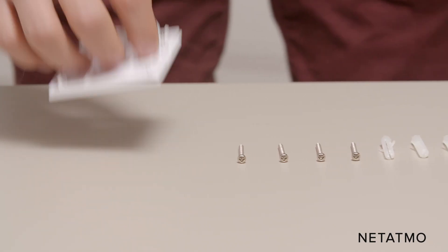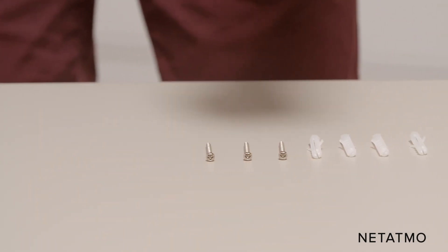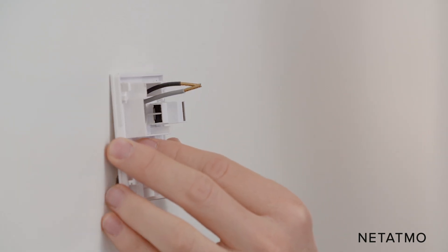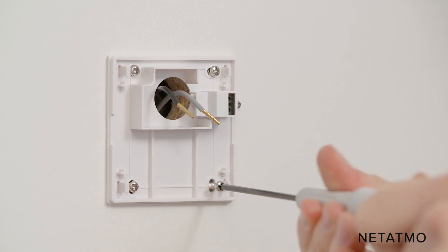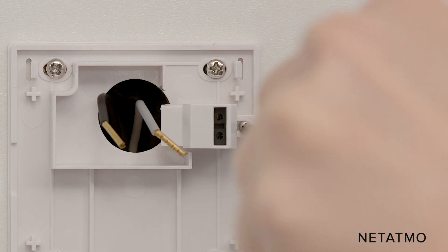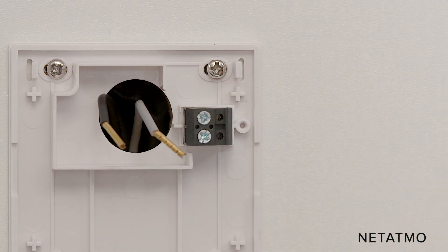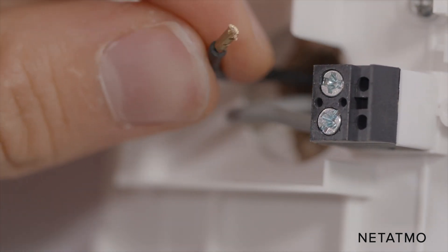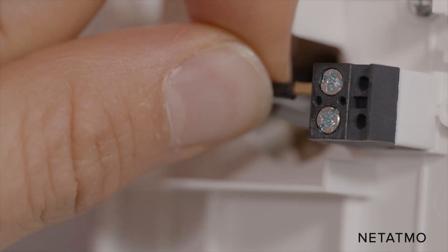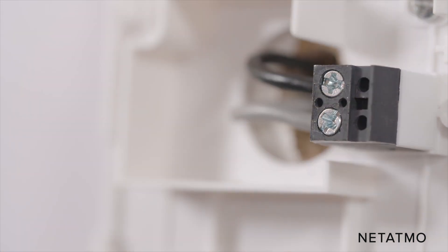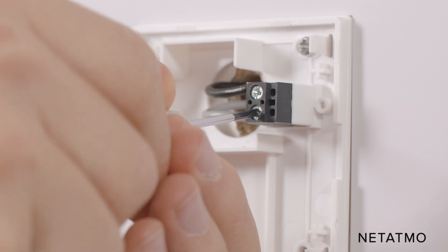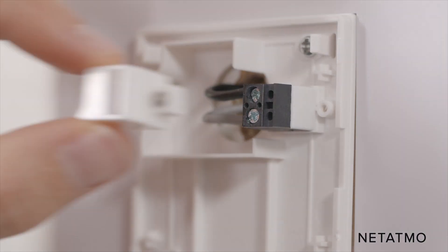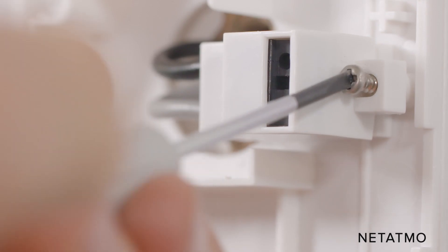Take the wall bracket and the screws provided. Pass the control wires through the wall bracket. Screw the wall bracket to the wall. Remove the protection cover with a screwdriver. Screw the control wires into the electrical terminals. As there is no polarity on the control wires, you can put any of the two wires in either port. If your former thermostat used extra wires, the other additional wires have to be insulated. Place and screw the protection cover back onto the electrical terminals.